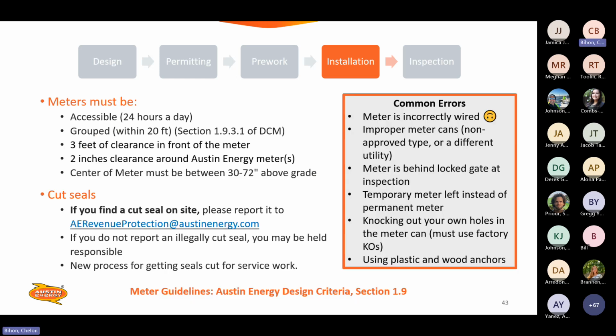Meters must be accessible 24 hours a day. They must be grouped within 20 feet, section 1.9.3.1 of DCM. 3 feet of clearance in front of the meter, 2-inch clearance around Austin Energy's meter. The center of the meter must be between 30 and 72 inches above grade. The dirt surface where you stand in front of the meter must be flat and clear within that 3 feet of clearance as well.